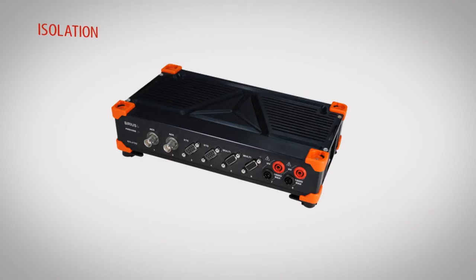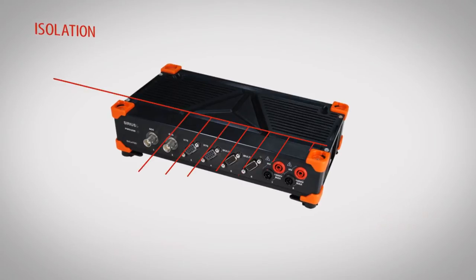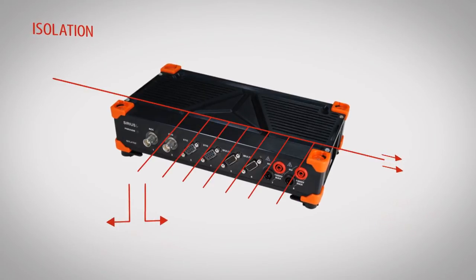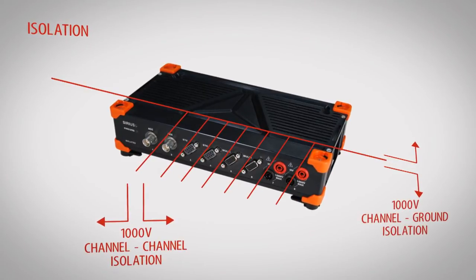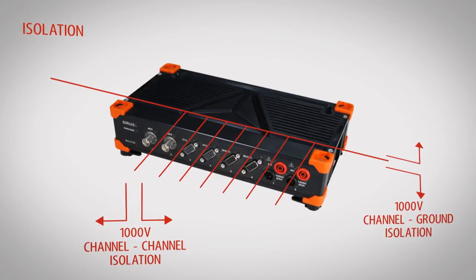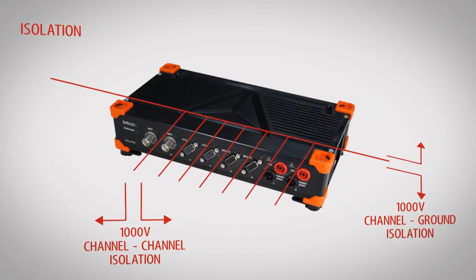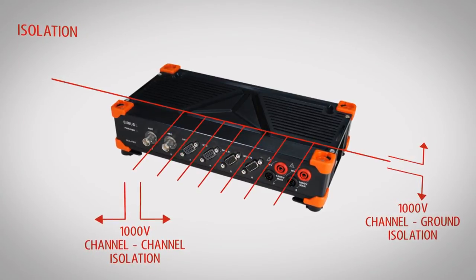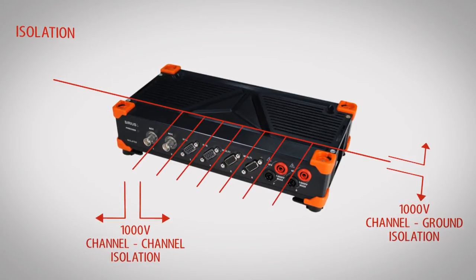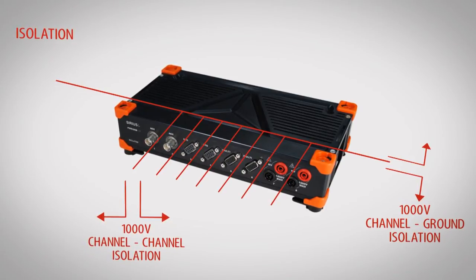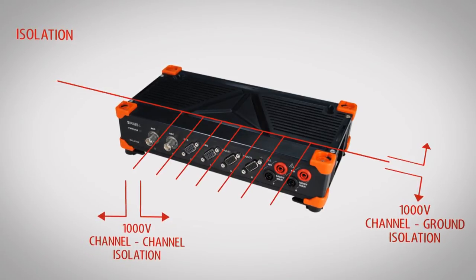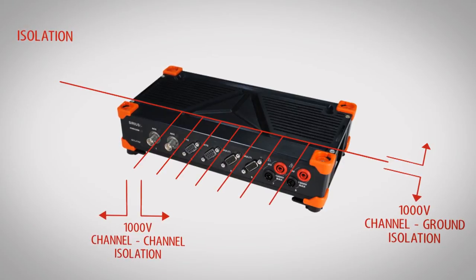Another important point of Sirius is isolation. Each input has 1000V galvanic isolation between the channels and from channel to ground. This means we have no problem measuring high voltage potentials and no problem with common mode voltages.